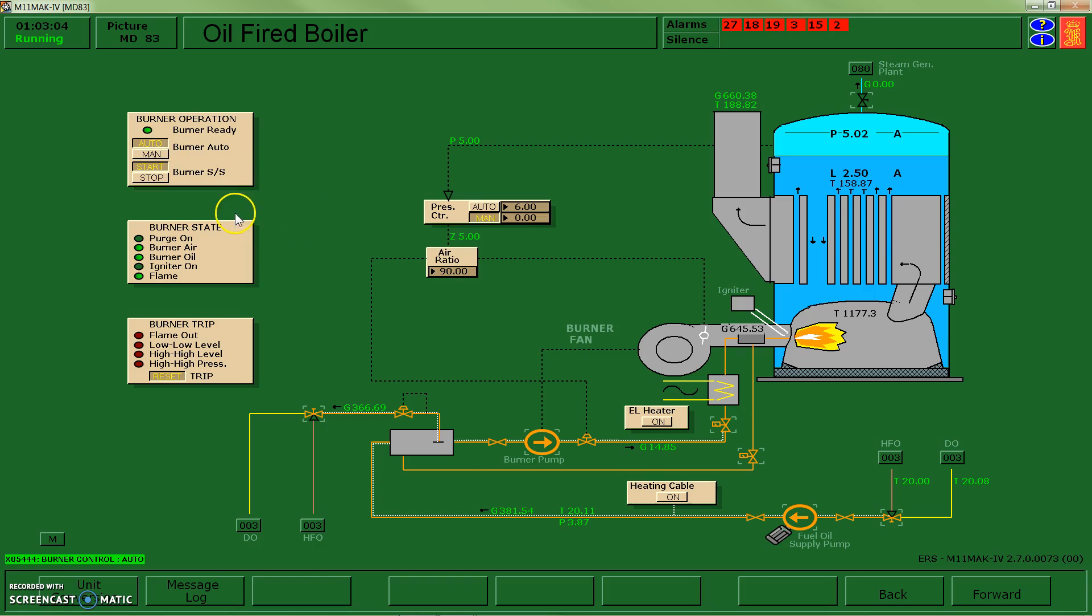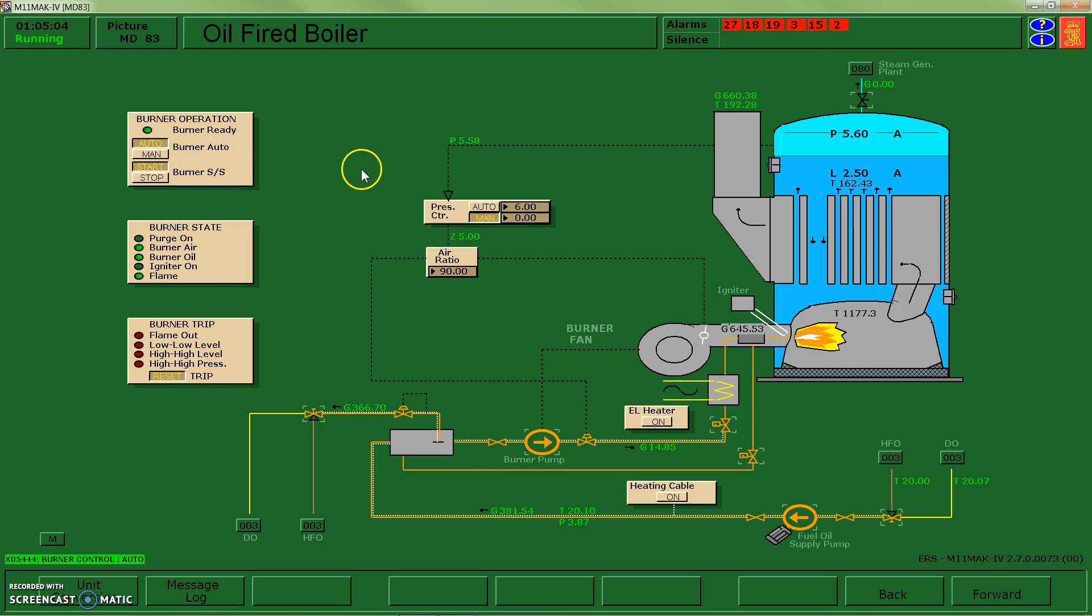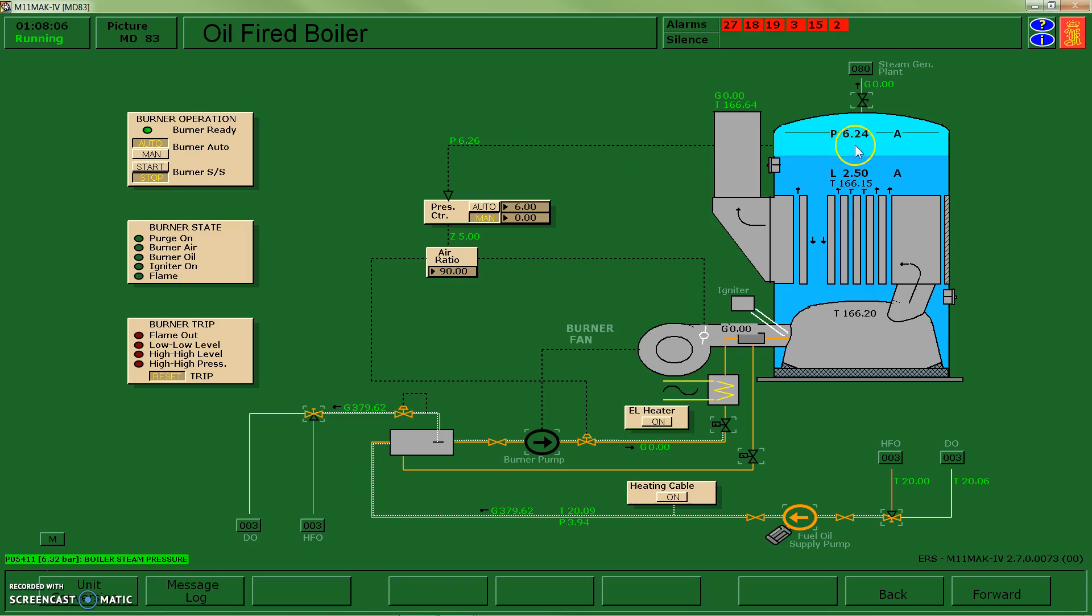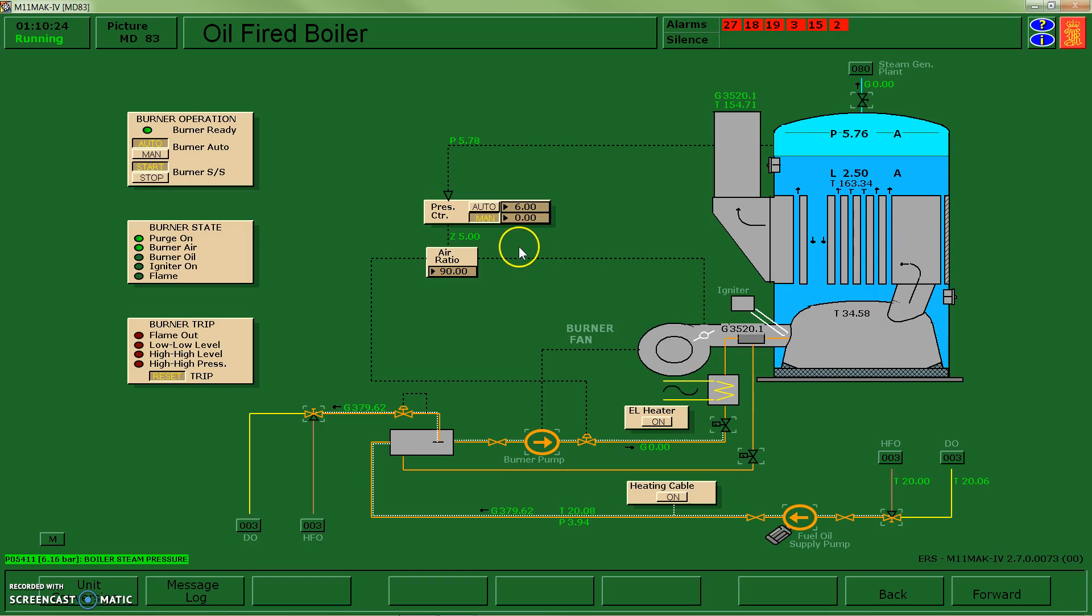This is sort of the safety piece, so before you walk away from the boiler, you want to make sure that something is going to automatically turn it off. You can see that I accidentally let the pressure go too high there, and the burner just turned itself off on its own, so that was an example of the safety device acting.